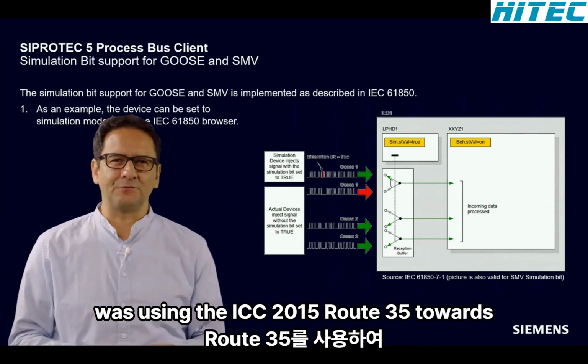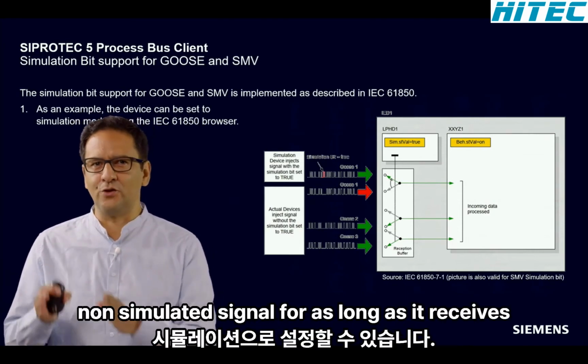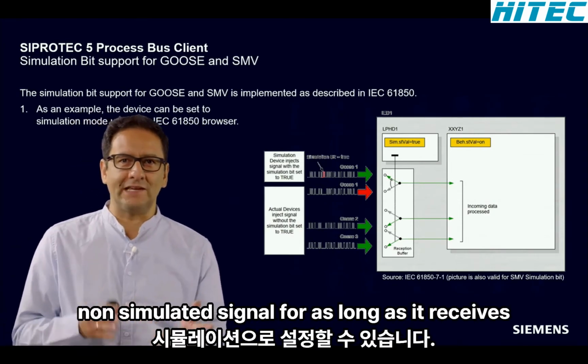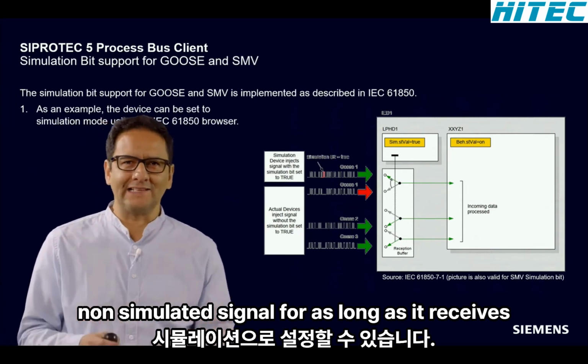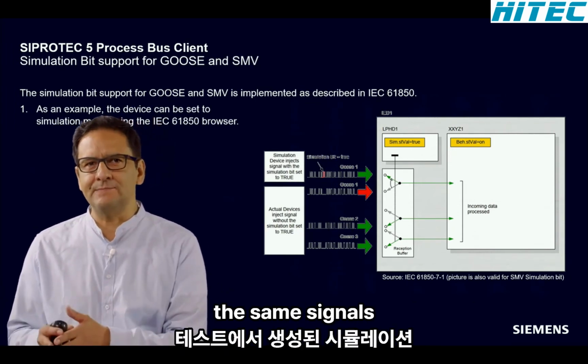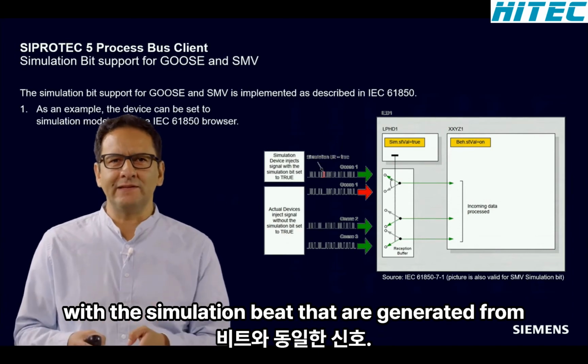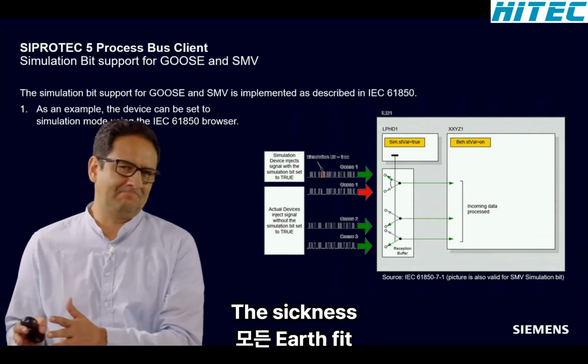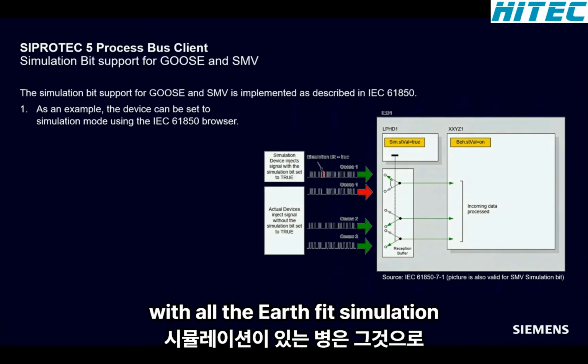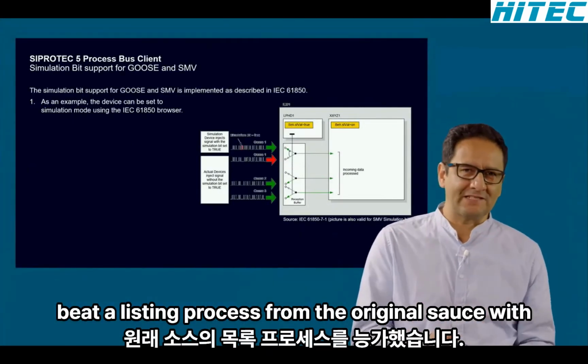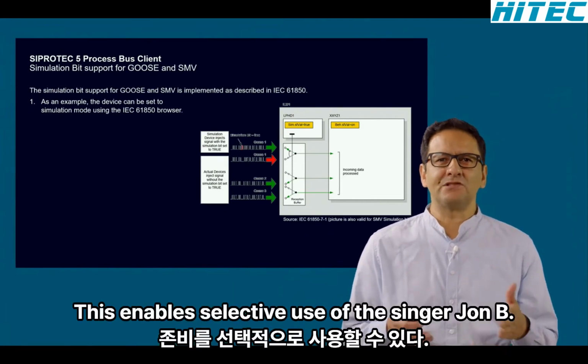In this mode, the device works with the original non-simulated signals, GOOSE, SMV, for as long as it receives the same signals with the simulation bit that are generated from a test set. The signals without a set simulation bit are still processed from the original source. With that, this enables selective use of the simulation bit.